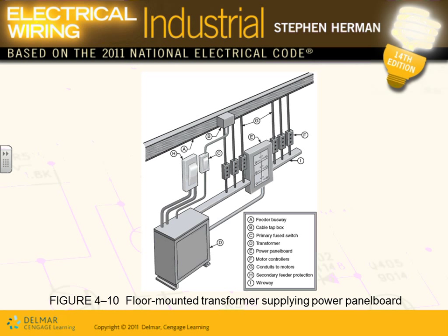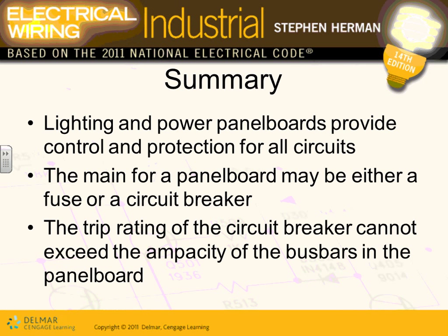And then from here, we're also feeding multiple motor loads. I know it's kind of goofy the way it's drawn, but really a bus duct feeds a disconnect that protects the transformer, which transforms the voltage to a lower voltage. The secondary of the transformer goes to a fused disconnect to feed this panel, and this panel is feeding through a wireway, this is a wireway actually, multiple controllers that control multiple motors. That's one way of doing business. Any comments, guys, any questions about this chapter?